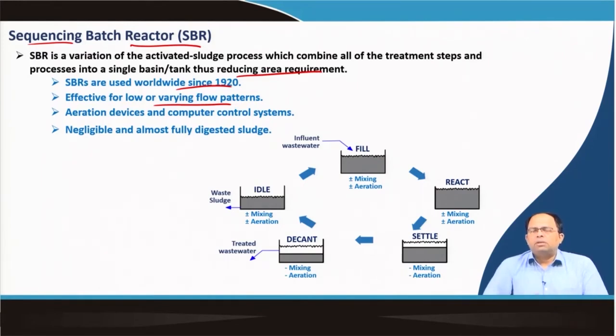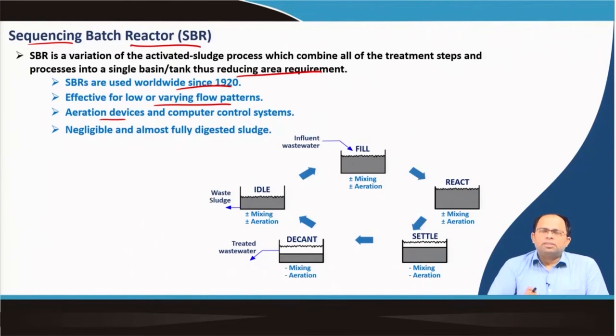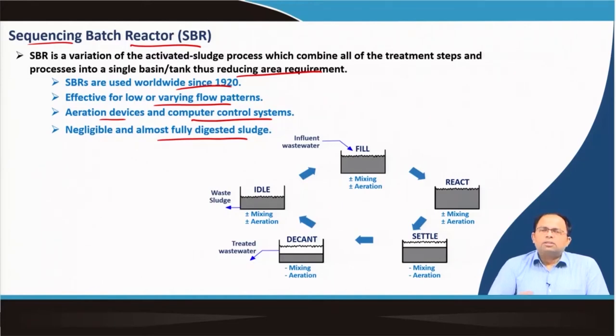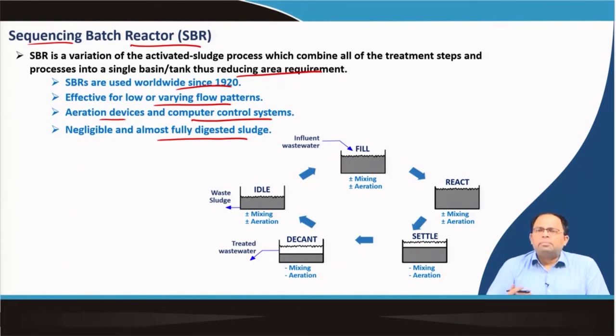SBR is not effective for very large volumes of wastewater — only for low volumes — but the aeration devices and the opening and closing of valves can all be computer controlled. This can be an automatic process in which sewage gets treated, and the final volume of sludge is very, very low because the organic matter is fully digested. That makes it very effective for decentralized treatment, and for large residential complexes it would be the best method.